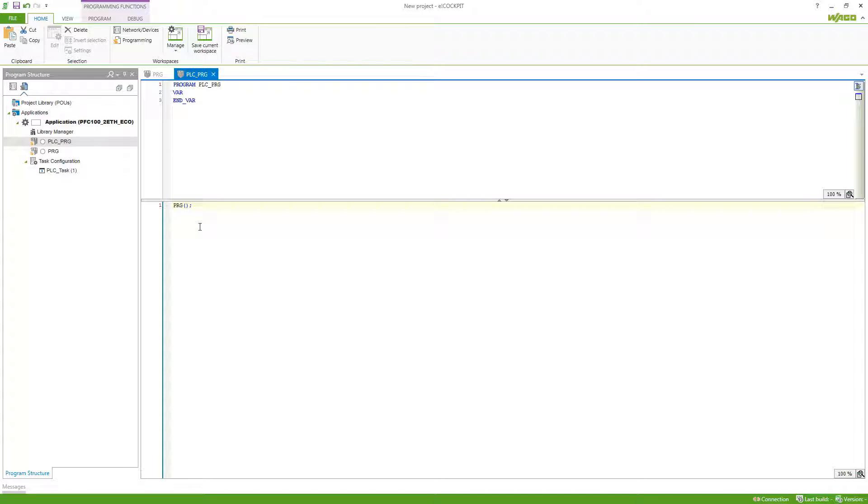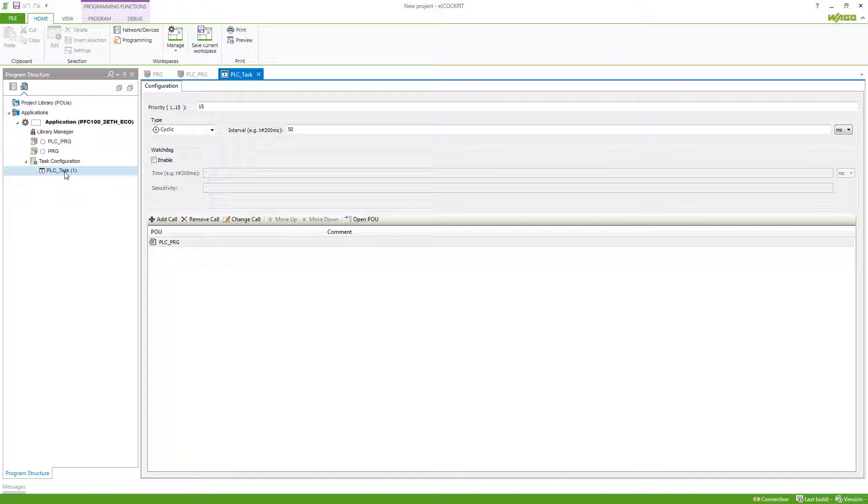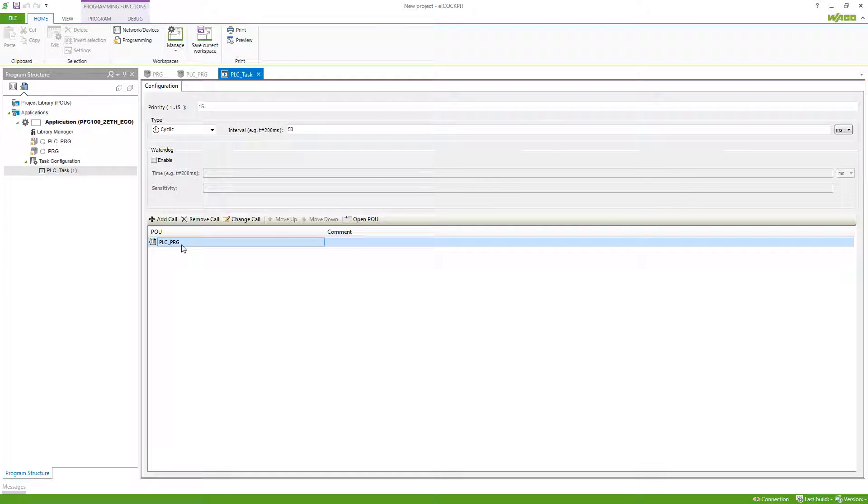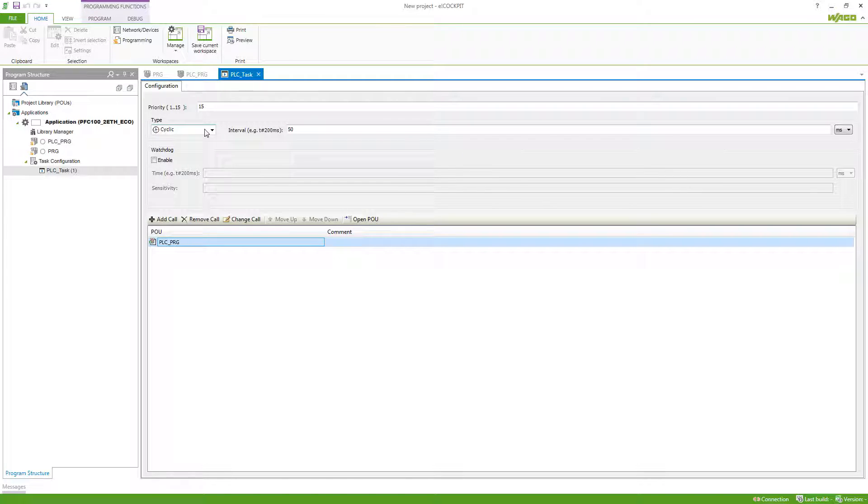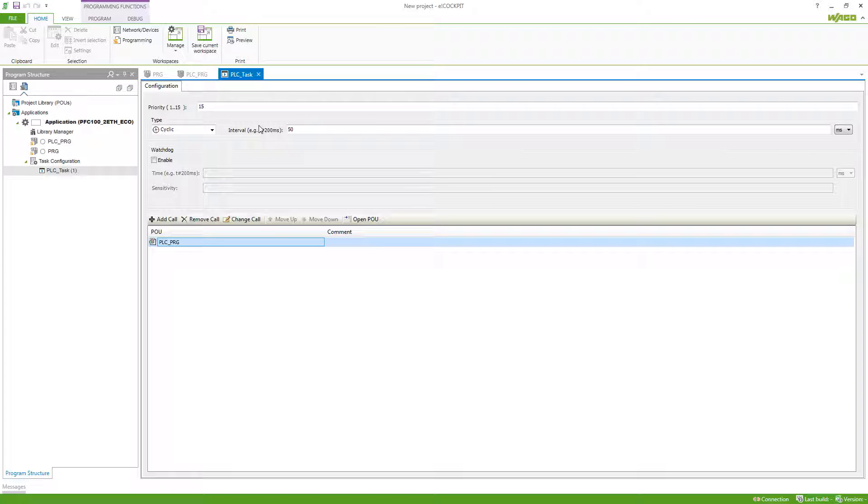If you create an application, you already have one task assigned, which is this one here. It is calling the PLC_PRG cyclic, you can see it right here, with an interval of 50 milliseconds. It also has a priority. So if you have several tasks, they can decide which task is being called first on your CPU. This one has a priority of 15, so a very low priority.